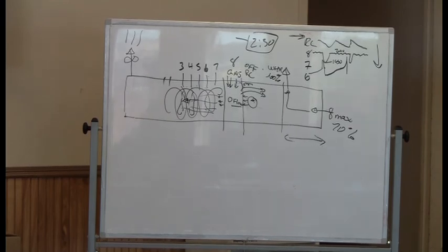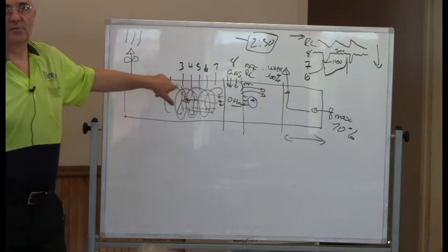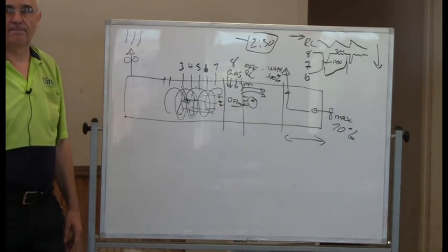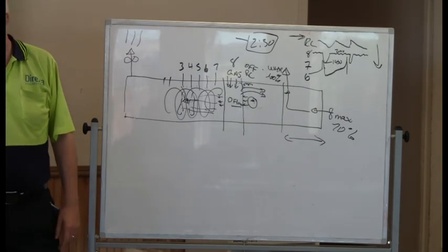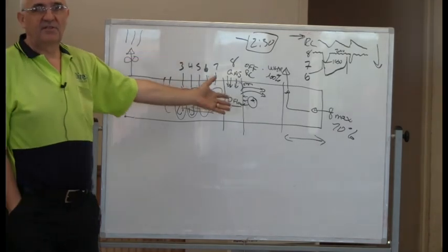And now because we're actually pulling it back down the tunnel and we're igniting it in 7 and 6, burning it off, that helps. We're really not having as much of an issue. Most of the issues we were having with grate and whatever is just dumb stuff in burner group 1, control and reliability. If it's balanced properly for the flashing, there is no reason to lose your temperature here. No reason, absolutely not. At the time, we were losing all the temperatures, though, it was such a big issue, we were back there. So you weren't getting the benefit of the gas. We were sucking it all back to the ground. Yeah, you were supplying a lot of energy.